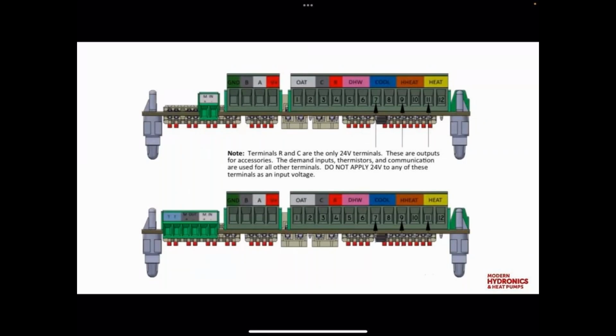So you could be really aggressive for domestic hot water on the backup, whether it be electric or dual fuel, or you could make it more aggressive in the space heating mode or vice versa. So there's a lot of flexibility and a lot of options here. And having both options available, a standard TT dry contact output or this modulating output, just opens up the door to a lot of possibilities. John, do you have any input here for piping a boiler straight to the back of a geothermal heat pump and modulating the boiler?